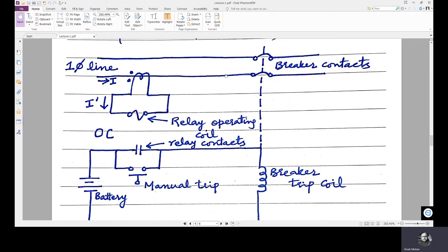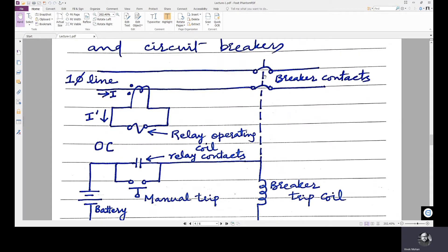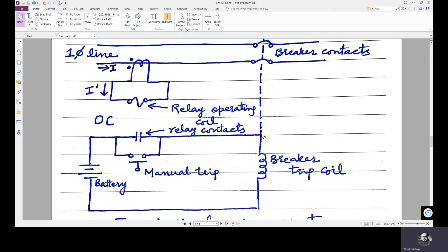In this example, the protection system protects a single phase line. The current flowing through the single phase line, if there is a fault, is detected by the current transformer and reproduced to a lower scale I dash. I is the actual current through the power circuit, reproduced to I dash which is at a lower level at which the relay operates. If a fault is sensed, the normally open relay contacts close and electrically complete this circuit. When this circuit is completed, the breaker trip coil is energized and the breaker contacts are opened, so the faulty component — the line itself — is isolated from the system. This is a simple overcurrent protection scheme to demonstrate the working.